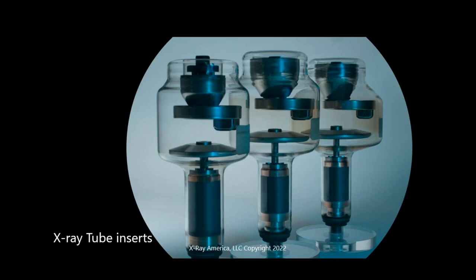I'm going to get into one of the very basic ones. So this is the critical component in an X-ray tube. It's an insert. The inserts are typically made of glass or have metal components or metal ceramic components. But in these rotating anode tubes, these are the tubes that would go into a RAD system, a mobile system, an RF system, a small cath lab.